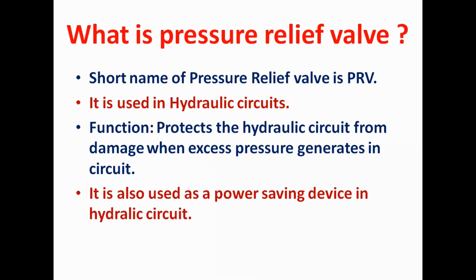Whenever there is excess pressure beyond the design pressure in the circuit, this PRV releases the excess pressure by draining the oil from the circuit and maintains the design pressure in the hydraulic circuit. It is also used as a power-saving device. When actuators like hydraulic cylinders are at the top or bottom position, the hydraulic pump keeps running, causing pressure to rise beyond the design pressure. In such a condition, this pressure relief valve continuously drains the oil to maintain the design pressure.